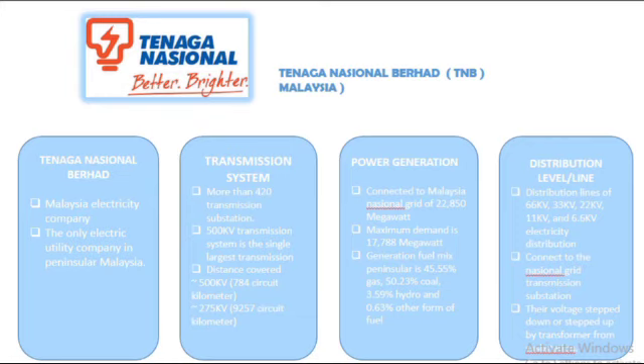For the distribution level or distribution lines, there are 66 kilovolt, 33 kilovolt, 22 kilovolt, 11 kilovolt, and 6.6 kilovolt electricity distribution, connected to the National Grid transmission substation. From the power station, the voltage is stepped up by the transformer at the substation. Then the electricity goes through the transmission line, and the voltage is stepped down by the substation using a transformer. Then it goes into the distribution line to the consumer. The distribution line acts as a safeguard for the consumer, making sure the voltage supplied is suitable.